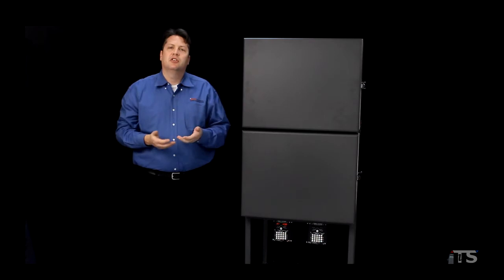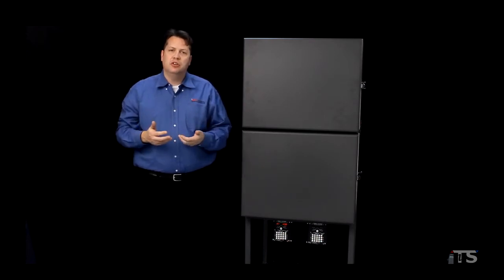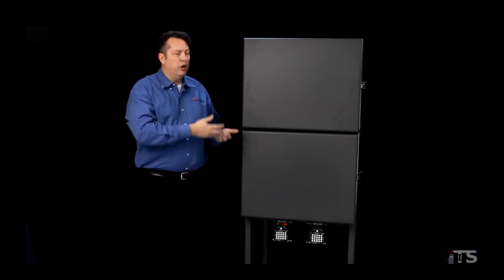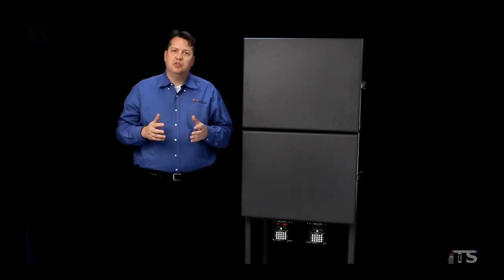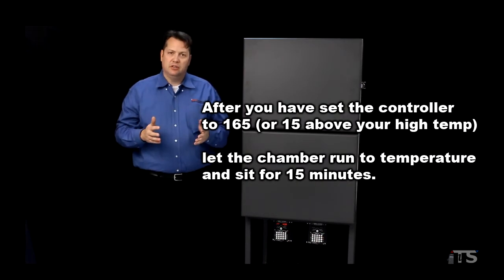After you've set your controller to 165 degrees, let the chamber run up to temperature and sit at temperature for roughly 15 minutes.